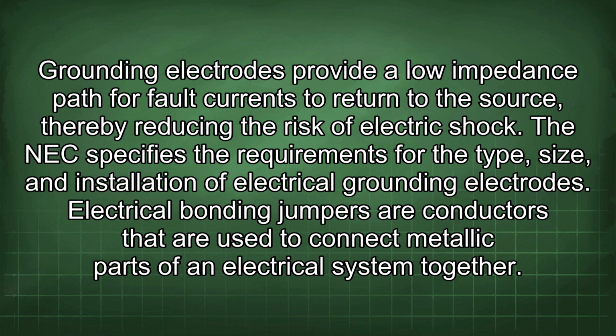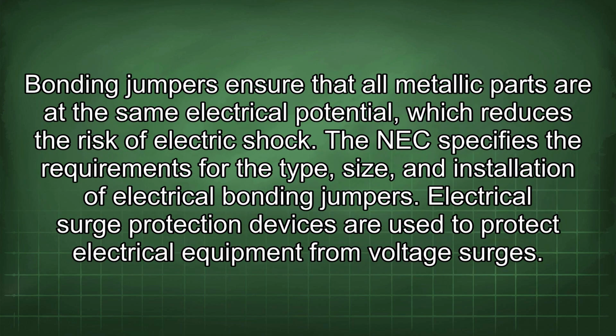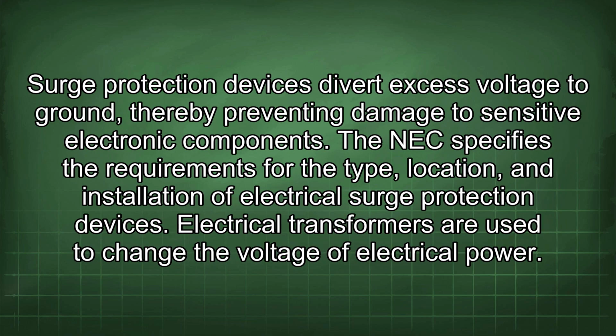Electrical bonding jumpers are conductors that are used to connect metallic parts of an electrical system together. Bonding jumpers ensure that all metallic parts are at the same electrical potential, which reduces the risk of electric shock. The NEC specifies the requirements for the type, size, and installation of electrical bonding jumpers. Electrical surge protection devices are used to protect electrical equipment from voltage surges. Surge protection devices divert excess voltage to ground, thereby preventing damage to sensitive electronic components. The NEC specifies the requirements for the type, location, and installation of electrical surge protection devices.